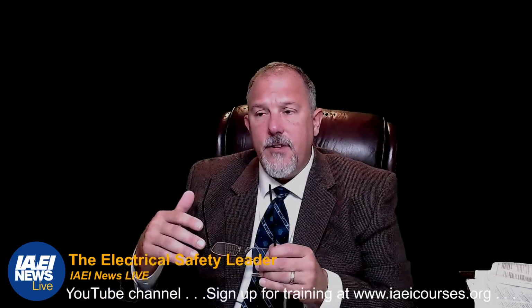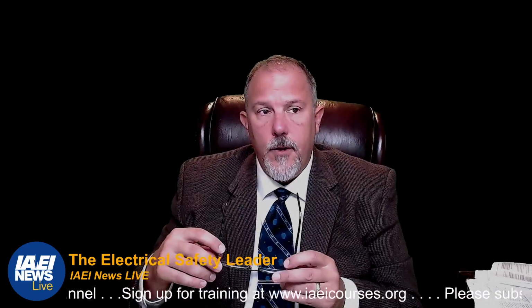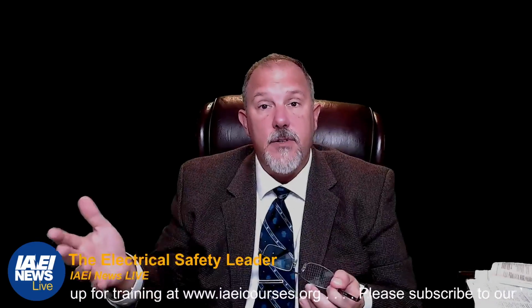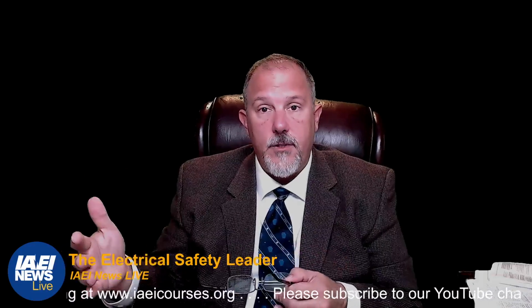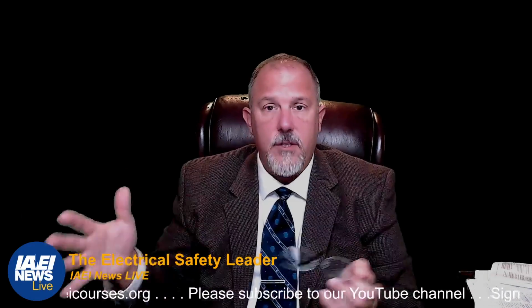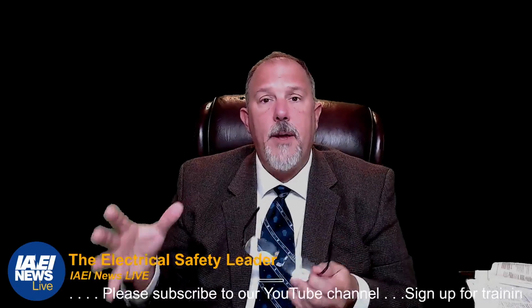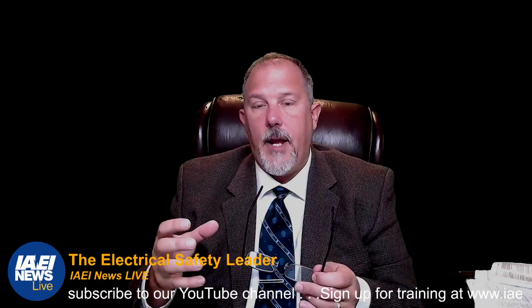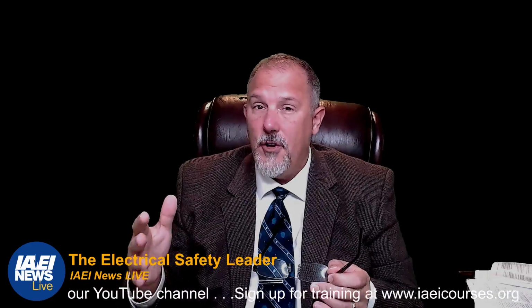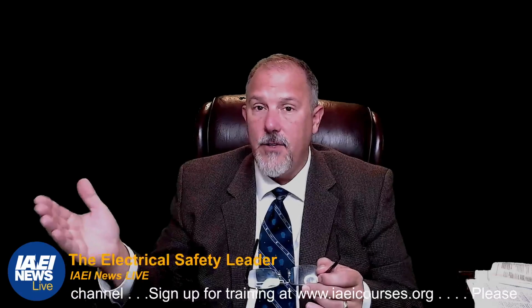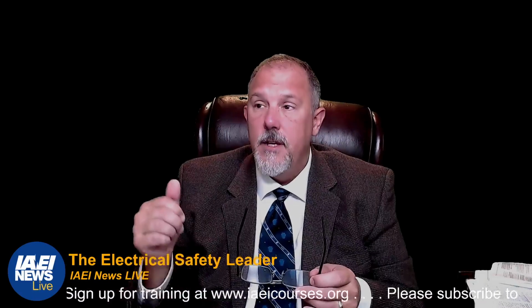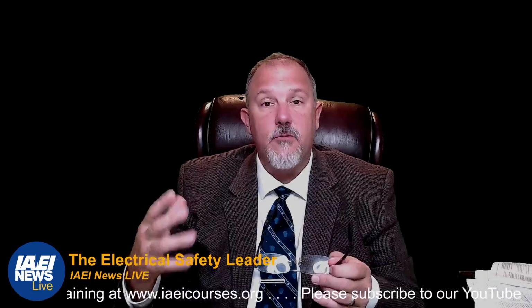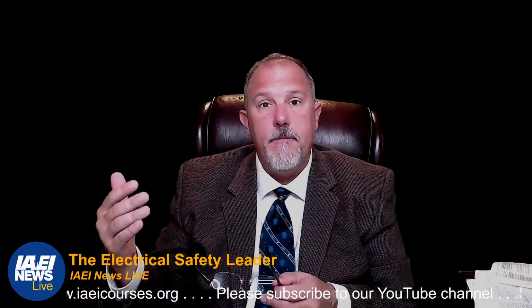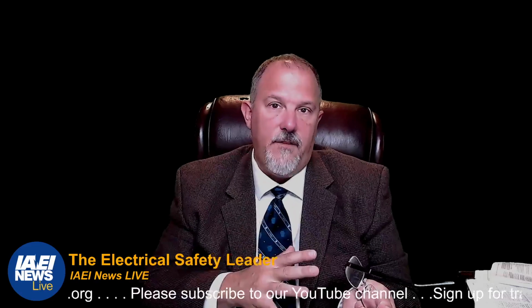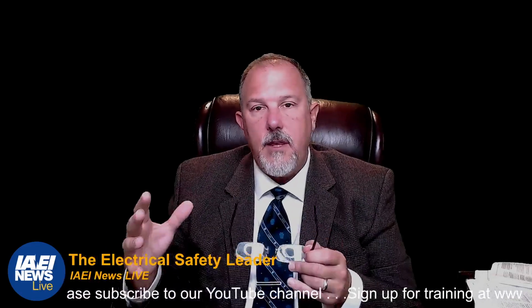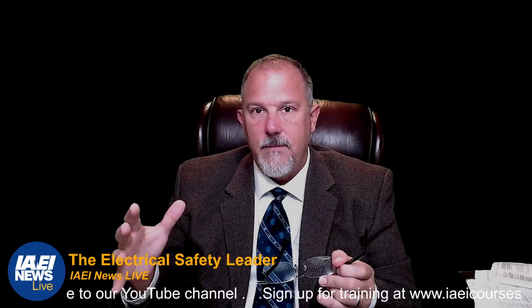When I start getting into after it's installed, I have to think about the maintenance of my panel boards and all my electrical equipment. But panel boards, since this is our discussion, the maintenance of that panel board, you're going to be dealing with any holes that are in the panel board. If you remove a conduit because you've taken a circuit out, make sure you plug all of those holes. Make sure that the integrity of the structure, if it's rusting, if it's in an environment that, let's say, is either a caustic environment or outside, make sure that the integrity of the box is still there.